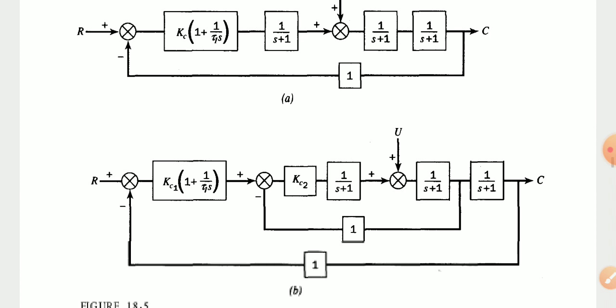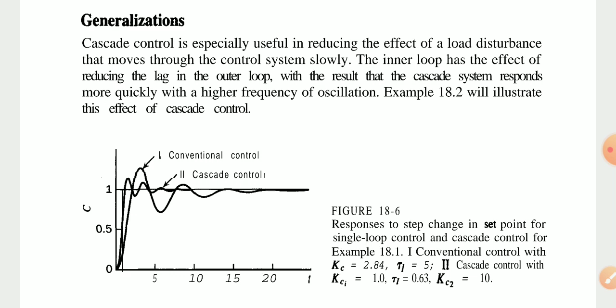Cascade control is especially useful in reducing the effect of a load disturbance that moves through the control system slowly. The inner loop has the effect of reducing the lag in the outer loop, with the result that the cascade system responds more quickly with a higher frequency of oscillations. Okay, simply draw graphically the system response to a step change in set point for a single loop control and a cascade control for this example. Conventional control with KC, TI, KC1 and TI1, KC2 values are given separately.